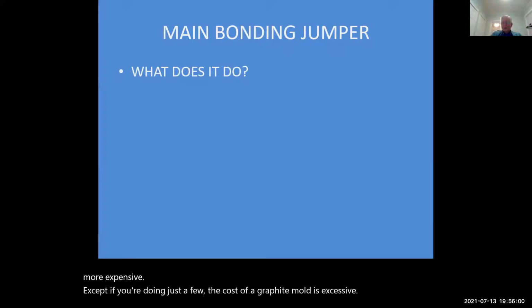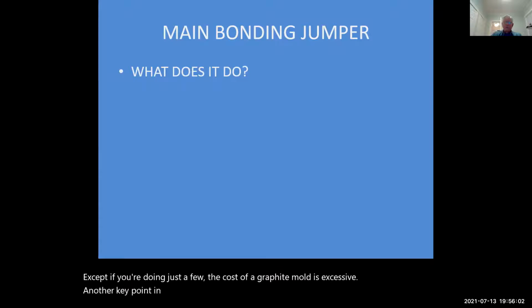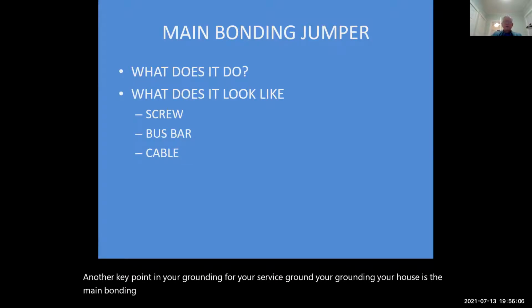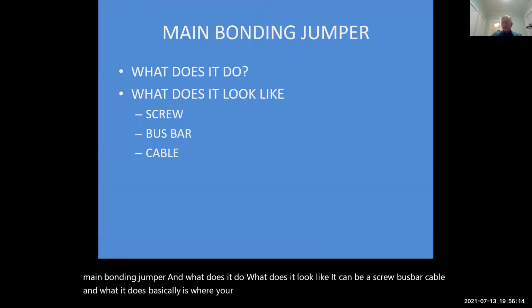Another key point in your grounding for your service ground, your ground in your house, is the main bonding jumper. What does it do? What does it look like? It can be a screw, a bus bar, a cable. And what it does basically is where your service enters your structure, your neutral and your ground are tied together. That's the only place where they should be tied together.